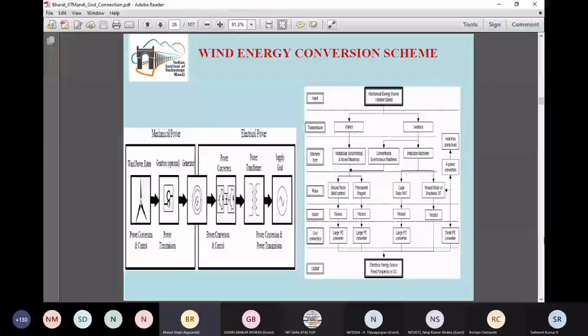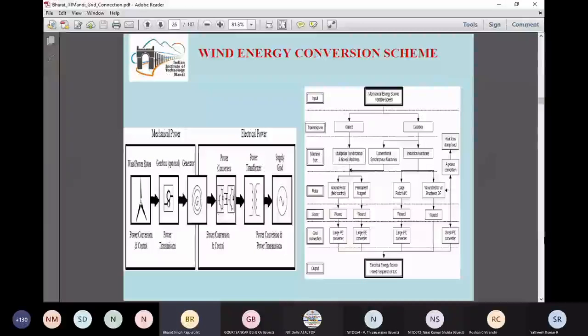Then the electrical generator produces energy or power which may not be suitable to be fed directly into the grid. So power electronic converters are there, which are able to process this electrical power as well as exercise a few controls, like making the system a variable speed system. Then a power transformer is there to match the voltage level. Generally these generators produce power at around 590 or 610 volt, and the power transformer steps it up to a transmission system level like 33 kV, 66 or 132 kV, so that this power can be transmitted through the grid. So this is a typical wind energy conversion scheme.